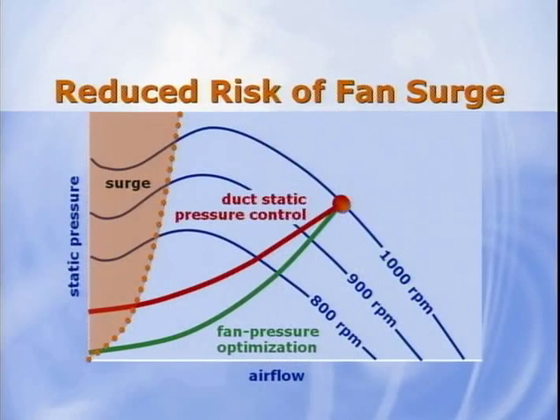A third benefit is the reduced risk of fan surge. By allowing the fan to operate at lower pressures at loads requiring reduced airflows, the fan operating point is kept further away from the surge region than when using conventional duct pressure control.